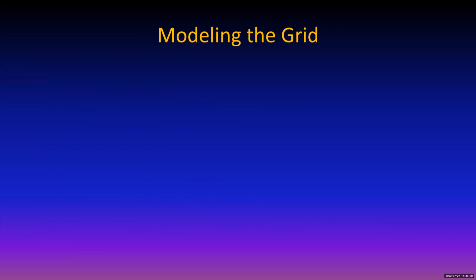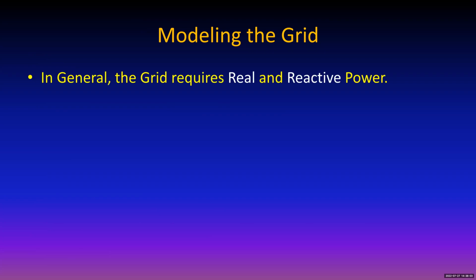So if you want to do things with the grid, it's nice to have a model for the grid. And to begin with, it needs real and reactive power. Reactive power is simply, if you turn on a motor, there are lots of magnetic fields in that motor, and those magnetic fields don't use energy themselves. They transfer the energy from the stator to the rotor, and in the process, that energy transfer is out of phase. The current is out of phase with the voltage, and so when current times voltage does not equal the power that you would measure with a watt meter, it means you've got some reactive power involved.